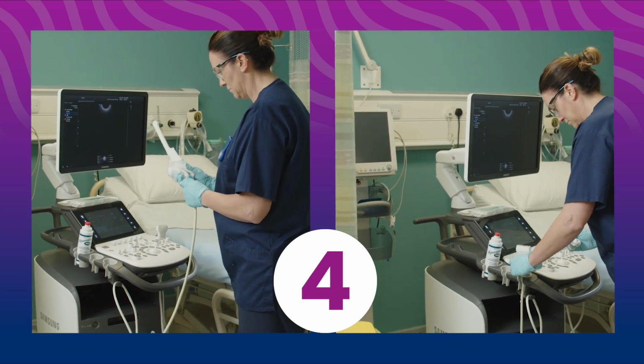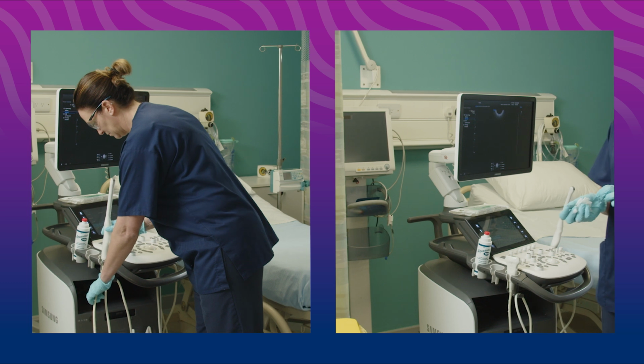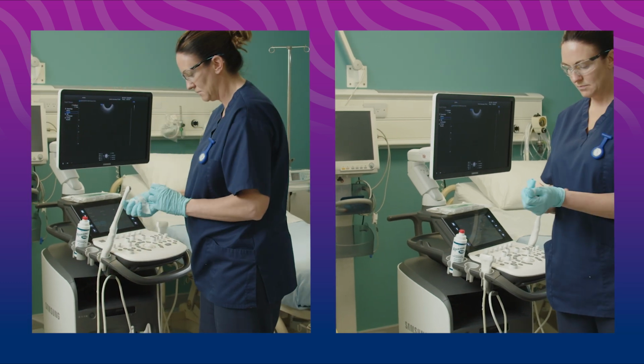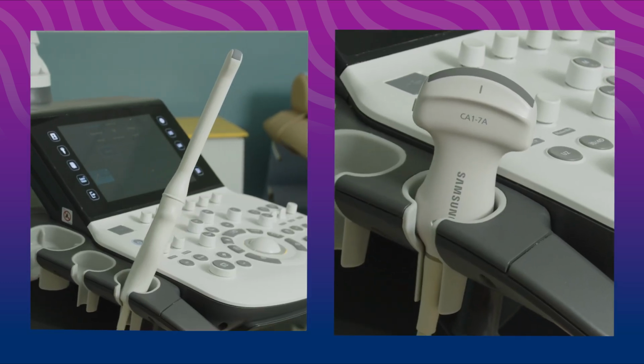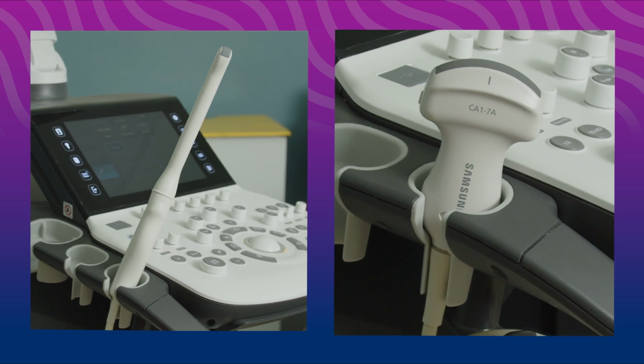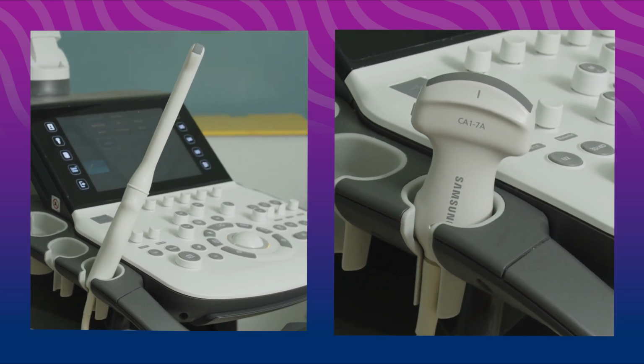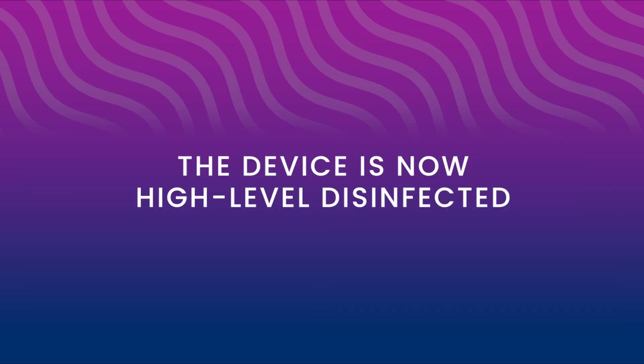After the device is wiped, place the probe on a clean space or back into the probe holder on the ultrasound system. Allow the probe to sit undisturbed for 2 minutes. After the 2-minute contact time has been observed, use a Tristel ULT wipe to remove any residue. The device is now high-level disinfected.